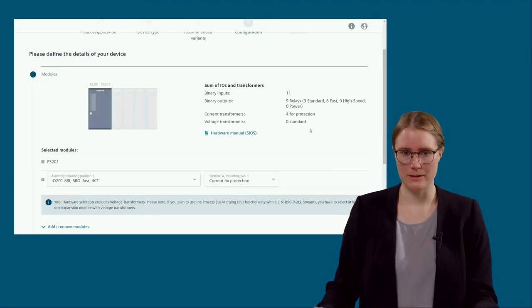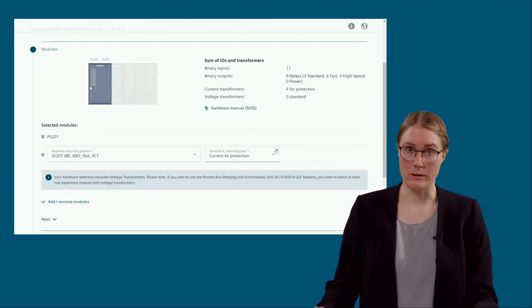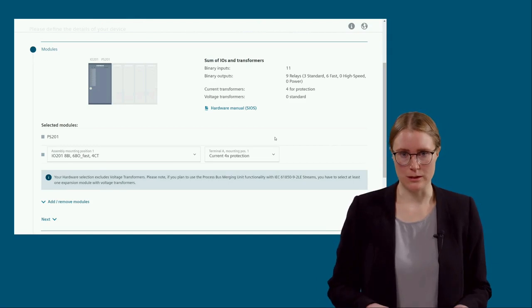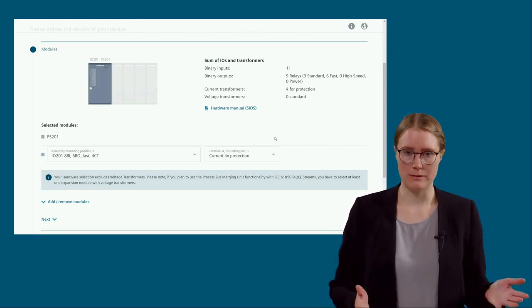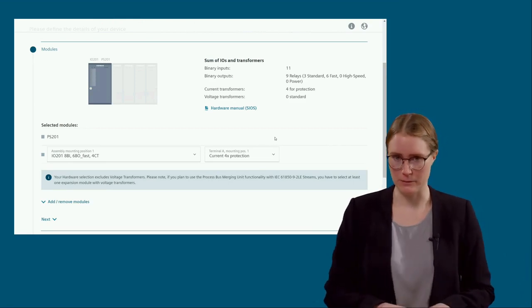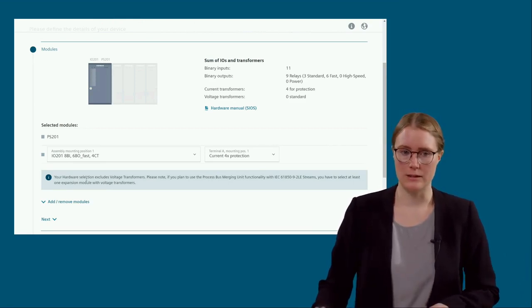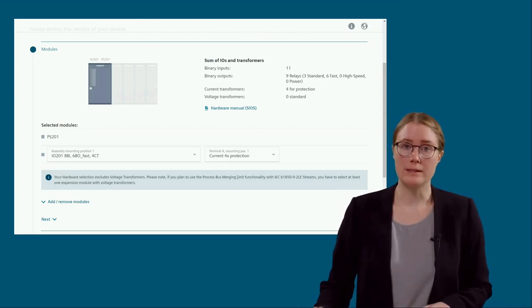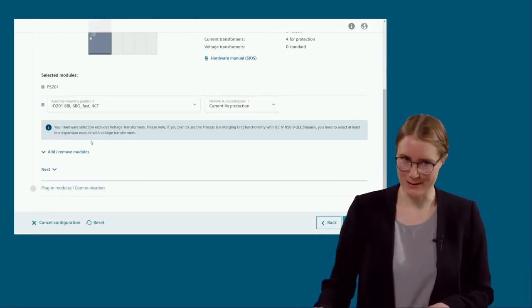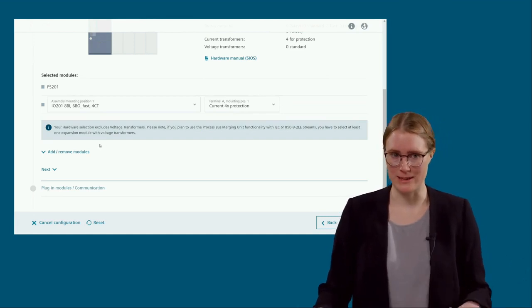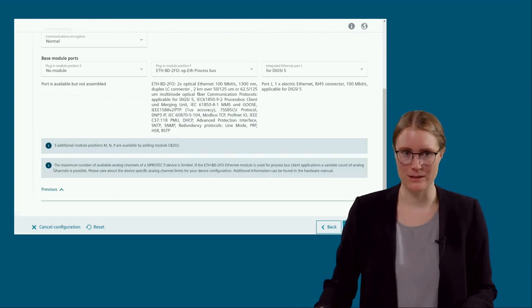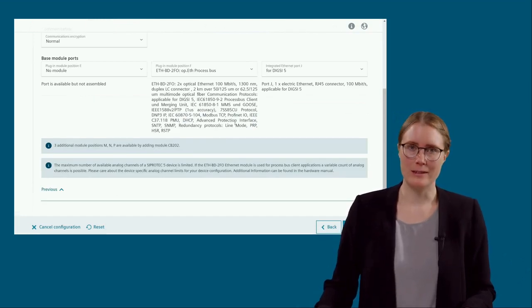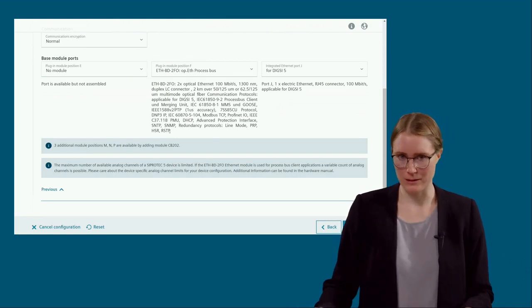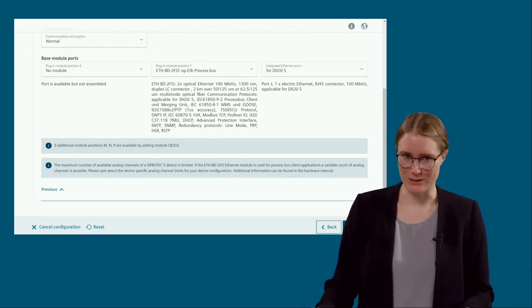So go to this. Here you see already one current input is included. If you have, for example, a coupler with 2 CTs, or you want to put more than one bay in one merging unit, then of course you can add an additional extension module and increase the number of current inputs here. Okay, but in our case, we have one merging unit for each bay. So I jump over this step and go to the communication modules. Here also one Ethernet module is already included. This is fine for us, and I go to the next step.